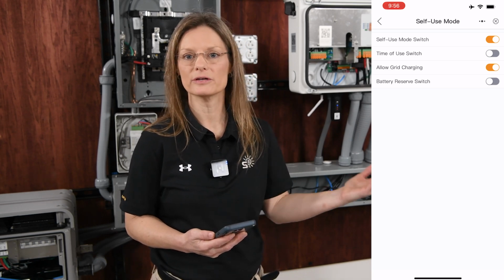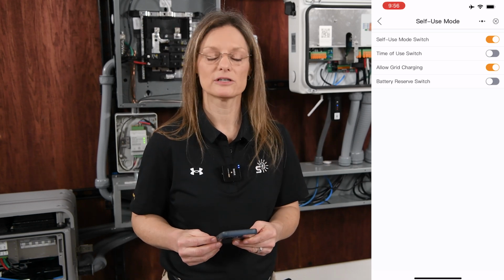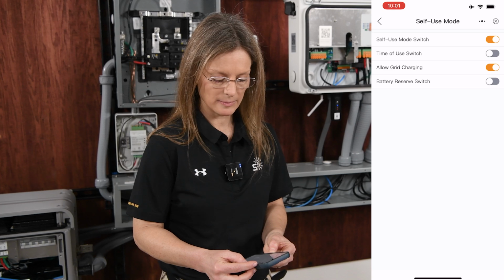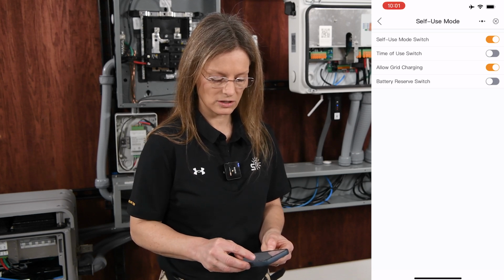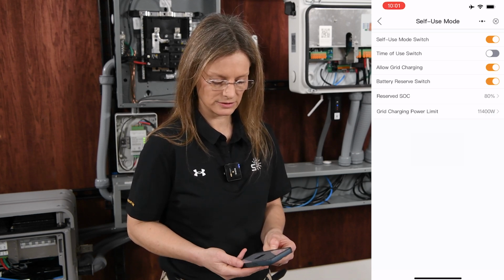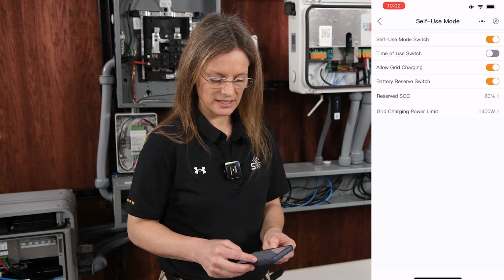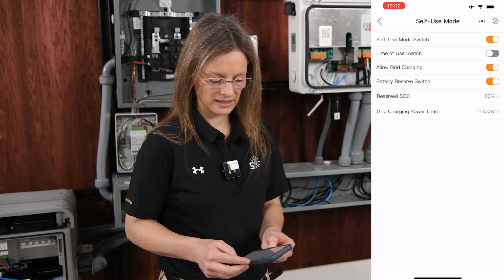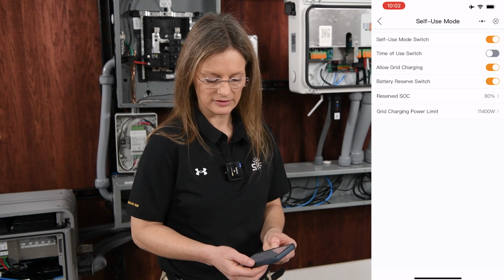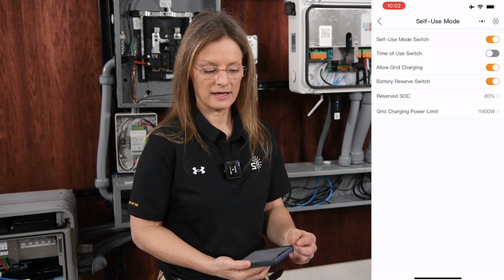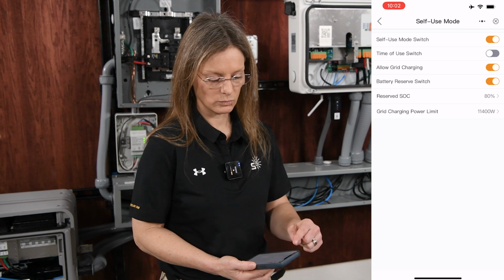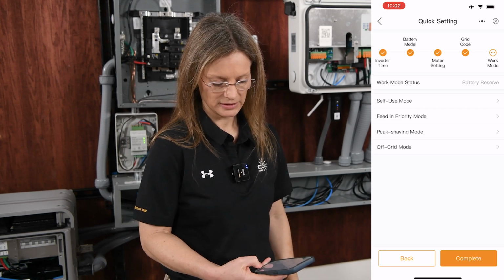Your next option is allow grid charging. This would just allow the grid to charge your batteries. The battery reserve switch, if you toggle this on, would allow you to set a state of charge percentage at which they would stop discharging as long as they were on grid. So with these settings, we're going to leave time of use switch off. We're going to toggle on battery reserve switch. We're going to leave our reserved SOC at 80% and leave the grid charging power limit at 11,400 watts. At this point, with our self-use mode settings set, we'll click the back button and we can say complete.